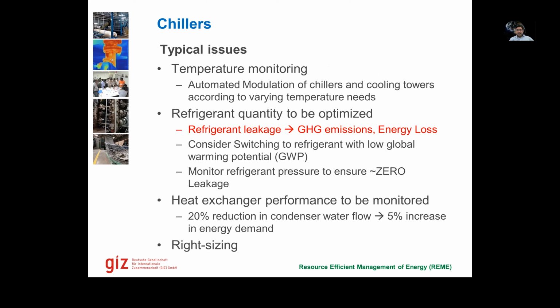Refrigerant leakage is a big issue. If we have a refrigerant type which is not a brine solution or a water system, but a gas refrigerant, these have huge global warming potentials. For some refrigerants, if 1 kilogram leaks, it is equal to 20,000 kilograms of CO2 emitted. So the global warming potential for refrigerants is very high. Some are also persistent, which means they stay in the environment for a very, very long time.